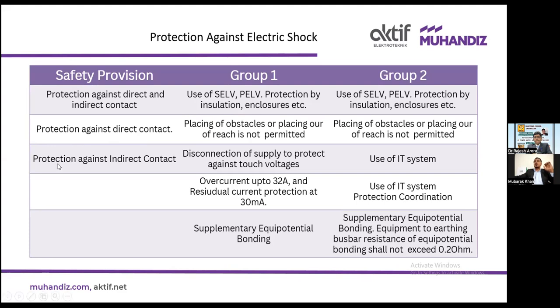Okay. Third is protection against indirect contact. For this one, in Group 1 locations, disconnection of supply must be there to prevent against touch voltages. Okay. And in Group 2 locations, we must use the IT system. What is the IT system? We will discuss in detail. And secondly, overcurrent protection up to 32 ampere can be used, and residual current protection up to 30 milliampere. Okay. For Group 2 locations, use of the IT system and protection coordination must be there. That also I will cover when I cover the IT system. Okay. Then the third part is supplementary equipotential bonding in Group 1 as well as Group 2 locations, with some extra provisions required for Group 2 locations.